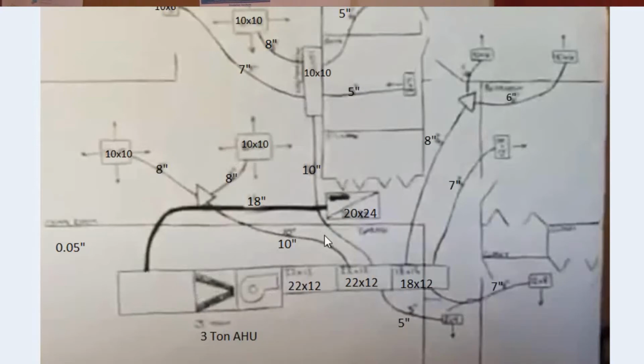Now, not only are you going to have low CFM, but your velocities in these trunks here, or I'm sorry, these branch ducts are going to be really low as well. Like I said earlier, I'm not terribly concerned with low velocity in the duct itself, okay? Where I do not want low velocity, though, is at the diffuser. All of these diffusers need a certain amount of velocity to get that air to disperse in the pattern that it is designed to disperse in, okay?